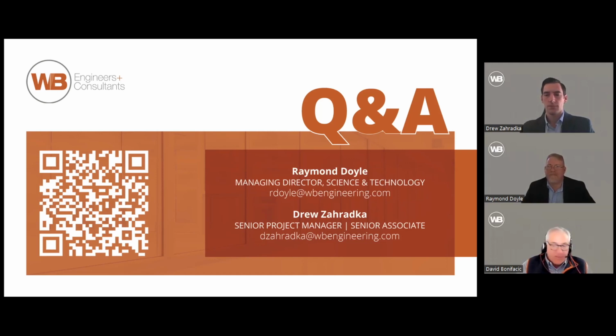Great presentation, guys. No disrespect to architects and engineers, I wish they did work more diligently on the operations side. It's difficult to get into things sometimes. Specifically, I have a question about filters. Is there a MERV rating on HEPA filtration? This has come up a few times at some of our properties, and trying to find HEPA filters for certain RTUs and air handlers is tricky. So certain MERV ratings have been recommended. I wanted to see if you can shed light on MERV ratings and or HEPA filters.